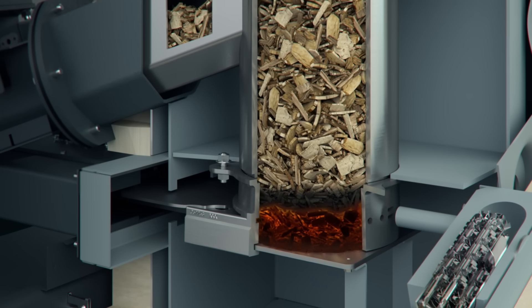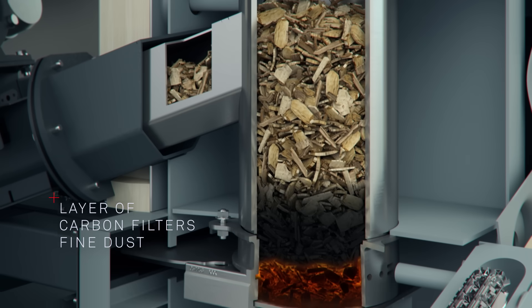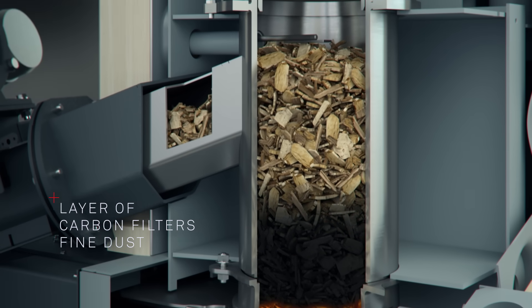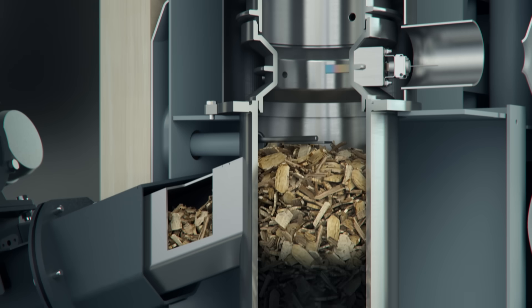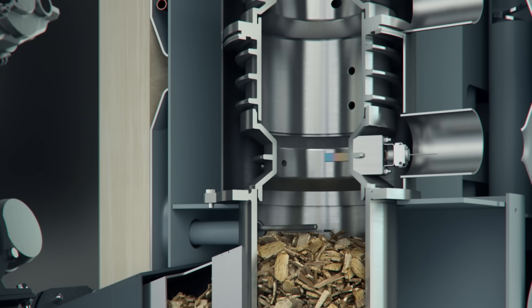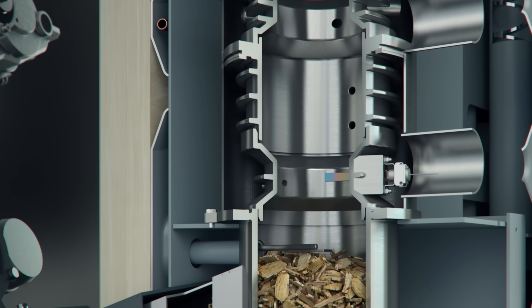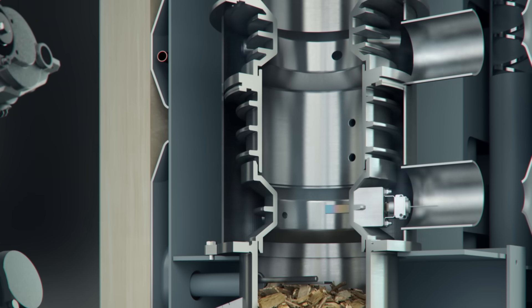This layer acts like an active carbon filter. Fine dust is filtered and retained within this charcoal layer. The combustible wood gases rise up from the ember bed through the layer of carbon and unburnt wood chip. After exiting the layer of wood chip, these gases are enriched with additional air and ignited by an energy saving glow igniter and burnt.